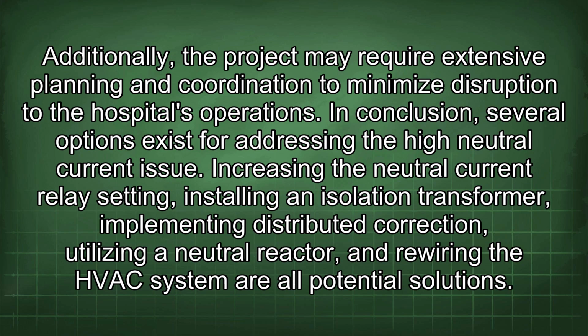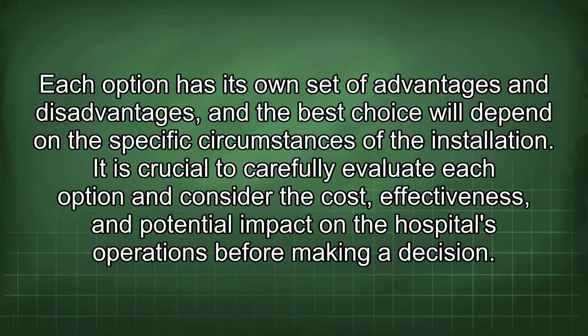In conclusion, several options exist for addressing the high neutral current issue: increasing the neutral current relay setting, installing an isolation transformer, implementing distributed correction, utilizing a neutral reactor, and rewiring the HVAC system are all potential solutions. Each option has its own set of advantages and disadvantages, and the best choice will depend on the specific circumstances of the installation. It is crucial to carefully evaluate each option and consider the cost-effectiveness and potential impact on the hospital's operations before making a decision.